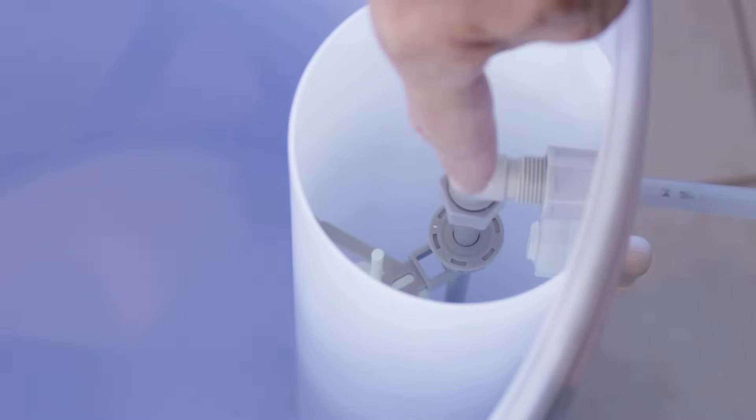Another potential cause is the brine level control, in other words the float that's here. Often I've seen it happen where this cap might have been lost and salt ended up going inside here and it actually clogs the bottom of the float. If you remove the float, take it out, wash it out and put it back in, ensure that it's working correctly. That's something else you could check.